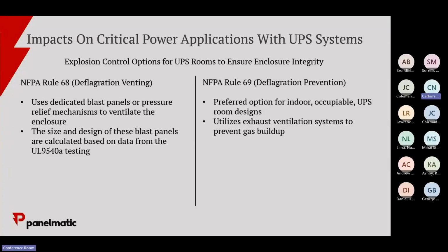Correct, the hard part is not many manufacturers are making lead acid batteries. VRLA was the old traditional use case, there are still ones out there, but most people are pushing toward lithium-ion. If you look at it from a dollar-per-energy standpoint, lithium-ion is way more cost effective and more energy dense. They also have a longer lifespan - a VRLA battery is typically a 7-year lifespan, where lithium-ion is 8,000 to 10,000 cycles depending on usage, so it's a 10 to 15 year battery.